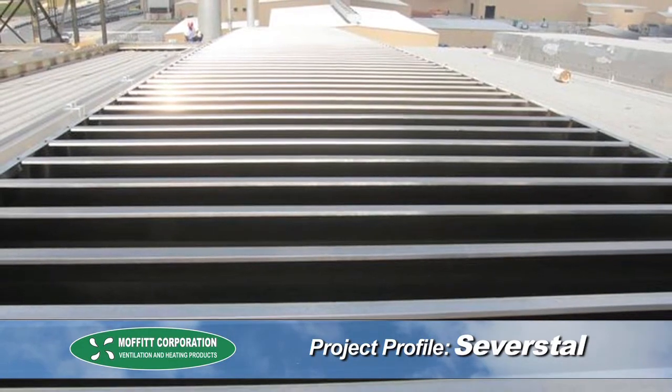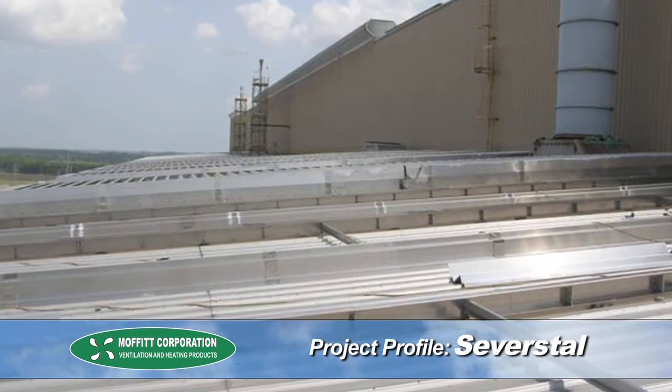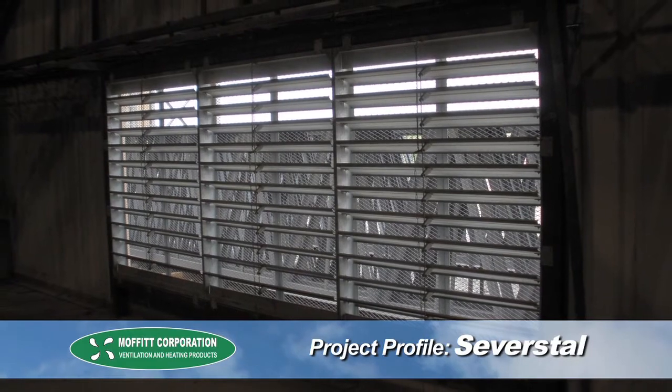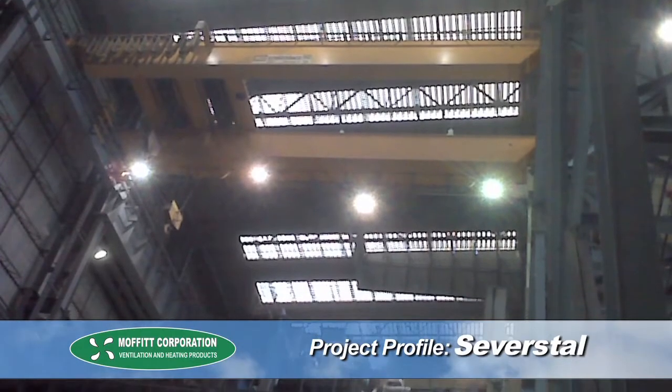Moffitt determined that the best solution would be a natural ventilation system, which consisted of 16 labyrinth natural ventilators located in key areas on the roof, as well as a number of wall louvers for supply air mounted down low. After installation of the system was complete, we tested the new conditions to see how big of a difference was made.